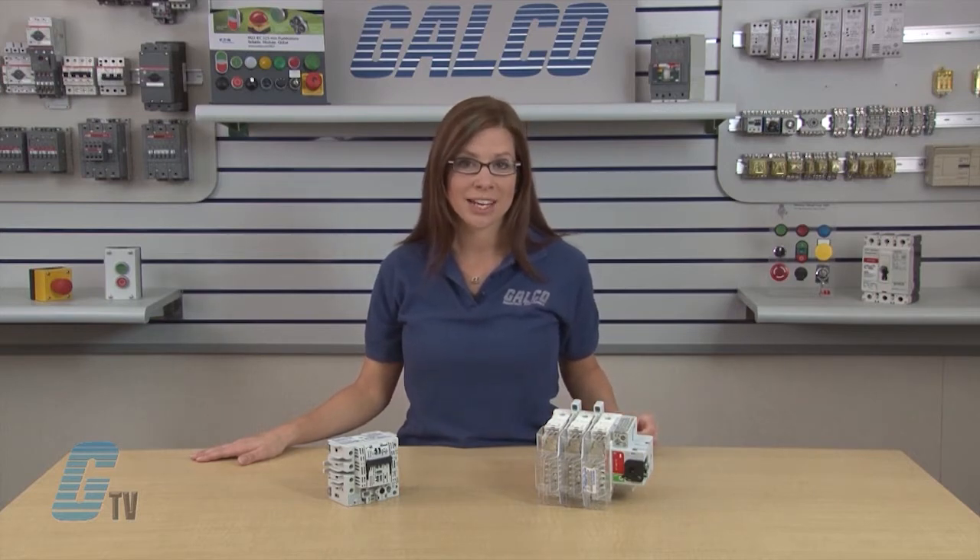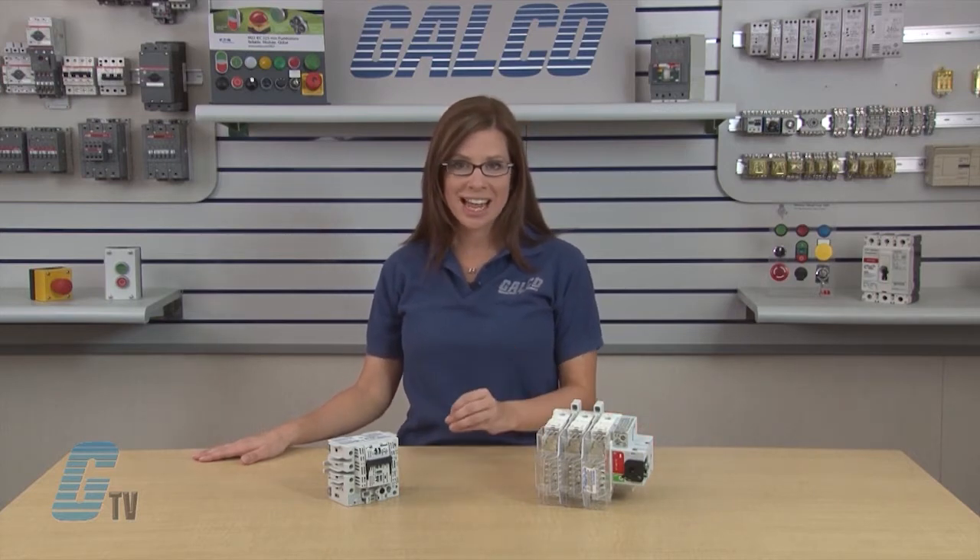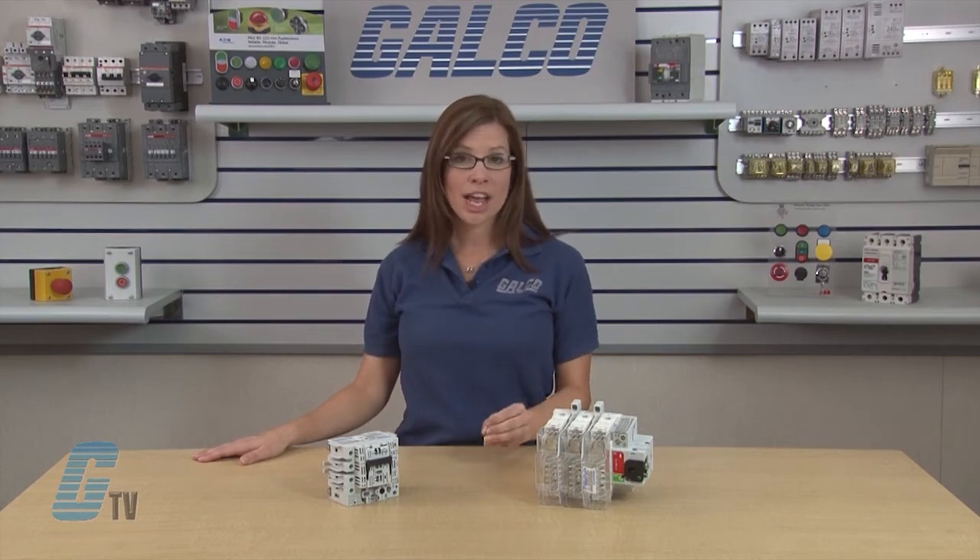All fusible disconnect switches are supplied with fuse covers and line side shrouding as a standard feature. These switches provide the ultimate in short circuit protection when used with Mersen's class CC, J or L fuses.